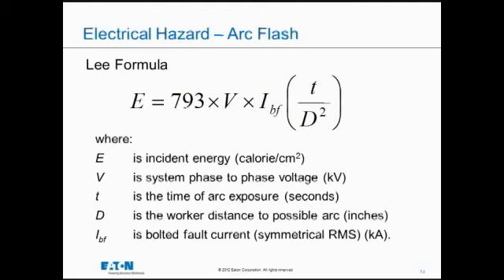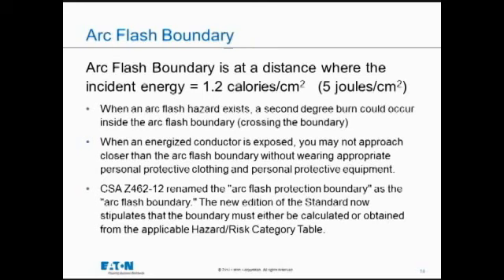And that formula calculates out an arc flash boundary. If I were to go back to this formula, and if distance was unknown, we left that as the unknown variable and plugged in all the other variables, volts, amps, and time, and then said, make that equal to 1.2 calories, we could get what's called the arc flash boundary.